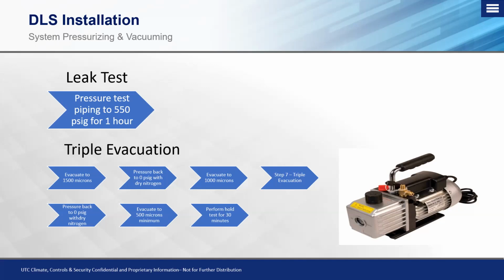Once it's held that 500 or 550 for an hour, then we can move into the triple evacuation. So once we've held our pressure, we're going to evacuate the system down to 1500 microns. We're going to wait about 2 to 3 minutes to make sure we're not getting any significant rises in microns. Once we've checked out, we're going to go ahead and pressure back the system to atmospheric, which is 0 PSIG with dry nitrogen. From there, we're going to go ahead and evacuate the system down to 1000 microns. We're going to do the same thing. Wait about 2 to 3 minutes. Once we've got to that 1000 micron point, to make sure we're not getting any significant rises, break the system back to atmospheric, which is 0 PSIG, and then finally pull the system down to 500 microns, and we need to at least hold 500 or better for 30 minutes.